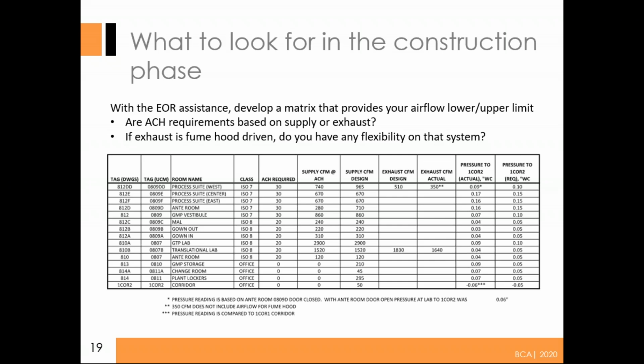Another thing to plan for these rooms is to work with the engineer of record and put together a little matrix like this. Here you've got the supply design CFM, but when you're going to be adjusting airflows for pressure, you need to know what flexibility you have. So what we usually request is a spreadsheet from the engineer that gives us what the airflow rate is relative to the air change rate required. You can see some of these rooms we weren't going to be able to adjust the supply, but we could in some of these other rooms. This allowed us to do some planning with the balancers on what rooms we could adjust.